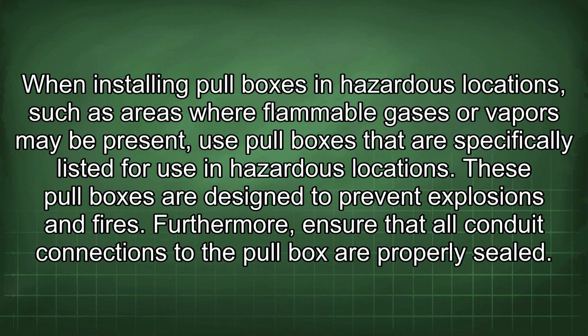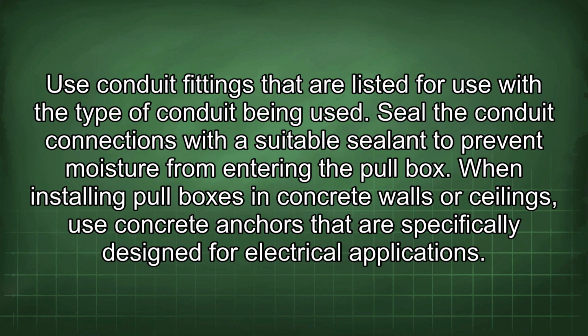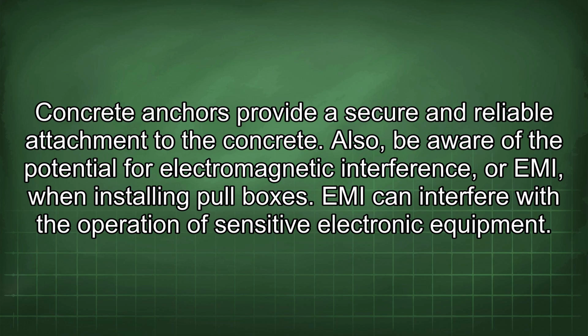Furthermore, ensure that all conduit connections to the pull box are properly sealed. Use conduit fittings that are listed for use with the type of conduit being used. Seal the conduit connections with a suitable sealant to prevent moisture from entering the pull box. When installing pull boxes in concrete walls or ceilings, use concrete anchors that are specifically designed for electrical applications. Concrete anchors provide a secure and reliable attachment to the concrete.